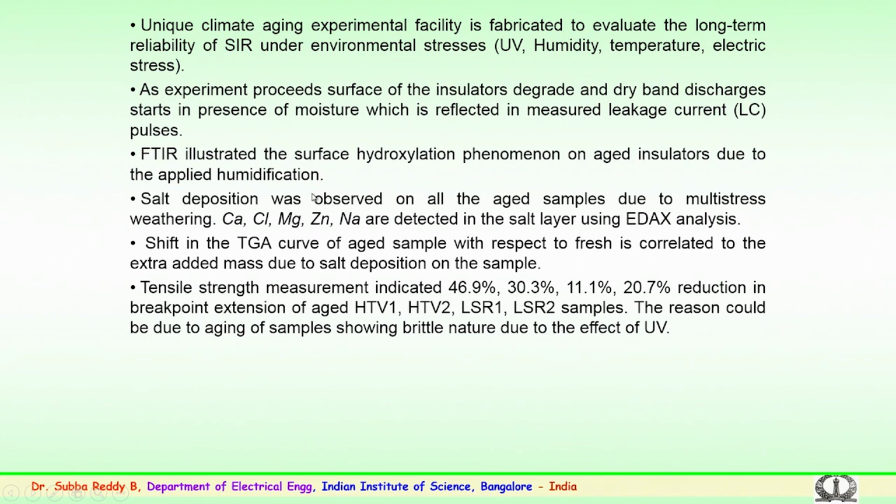Further, FTIR, that is Fourier transform infrared spectroscopy, studies illustrate the surface hydroxylation, particularly for the aged insulators at 500 or 1000 hours. This may be due to the humidification which has been applied on the sample. It was also observed that salt deposition was on all the aged samples due to multi-stress weathering, like Ca, Cl, magnesium, zinc, Na. These were all detected in the salt layer using the energy dispersive X-ray analysis over the period of time. These were prominent after the 1000 hours.